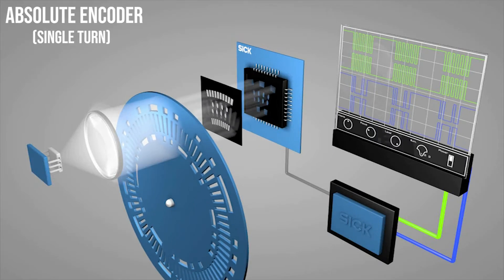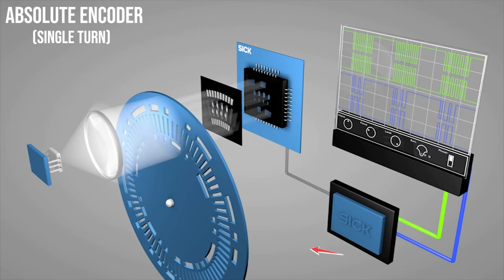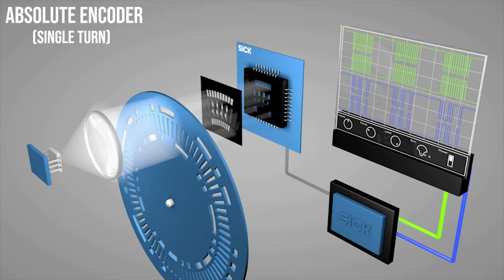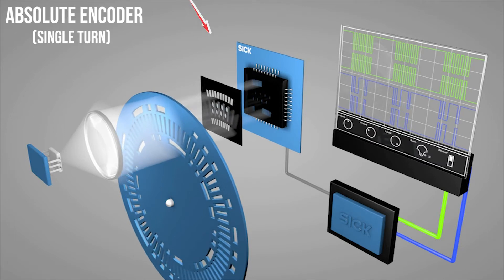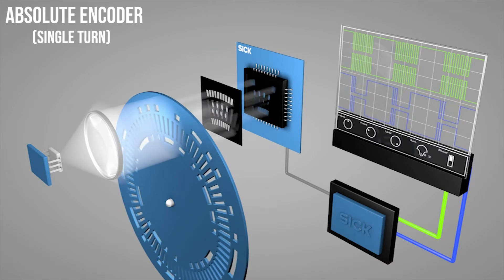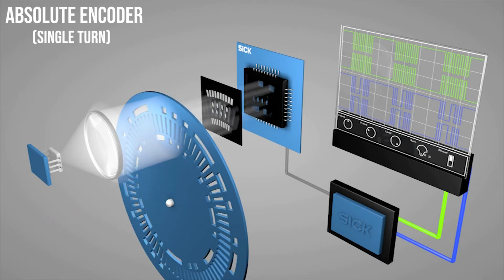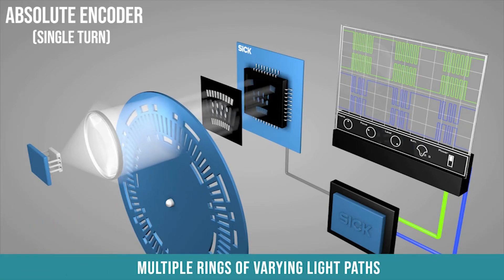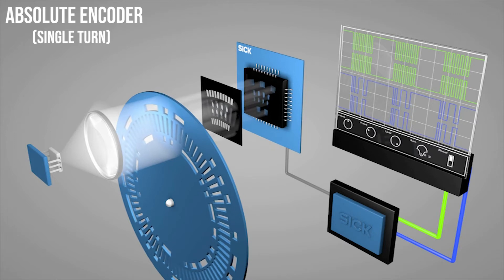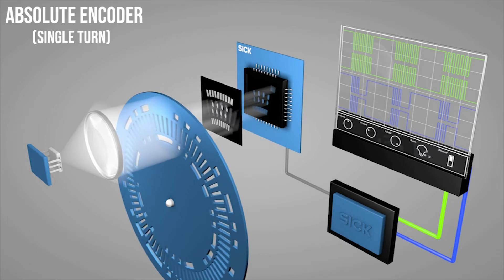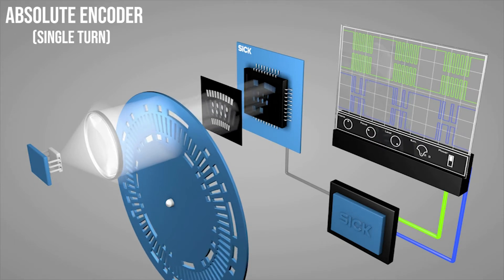Absolute encoders solve the problem of losing position during a power reset by having more data on the internal encoder wheel that indicates the precise location. Just like the incremental encoder, the absolute encoder is comprised of a light emitter and receiver, as well as a rotating disk with many little slots cut into it. You'll notice that the disk looks a bit different because it now has multiple rings of varying light paths. These light paths, or tracks, are all monitored individually like individual incremental encoders. At every position of movement on the encoder, these rings are uniquely lit up on the receiver creating an address.